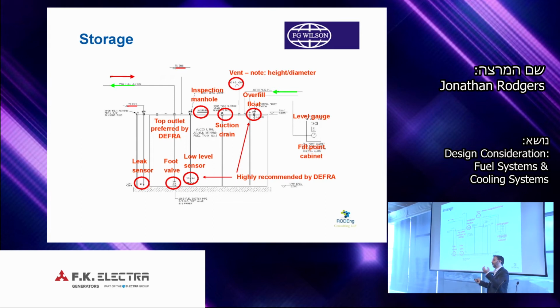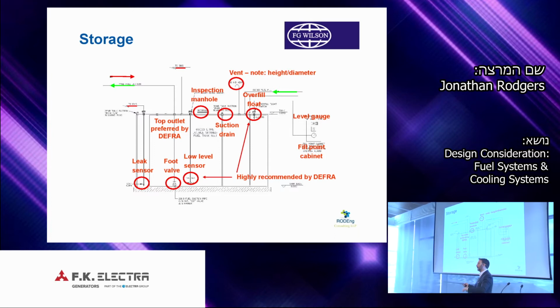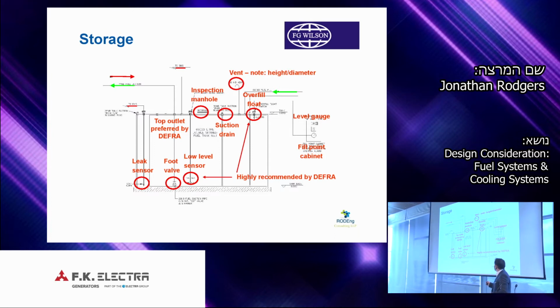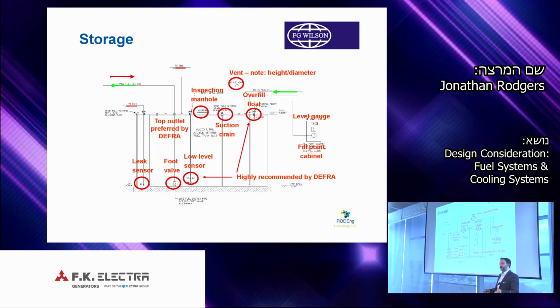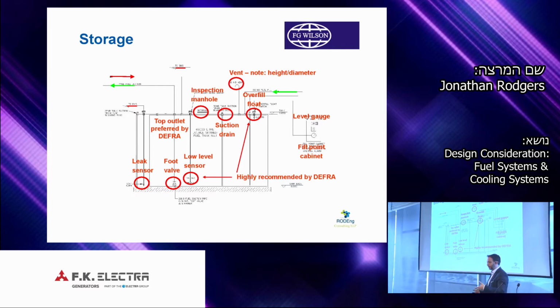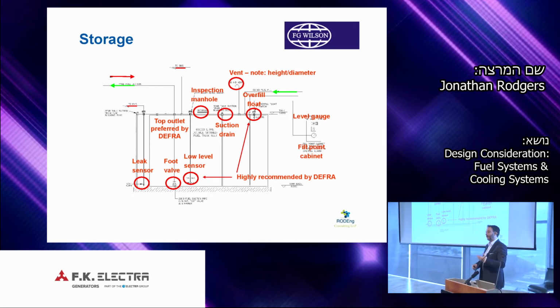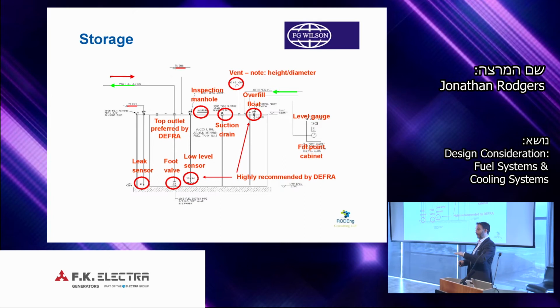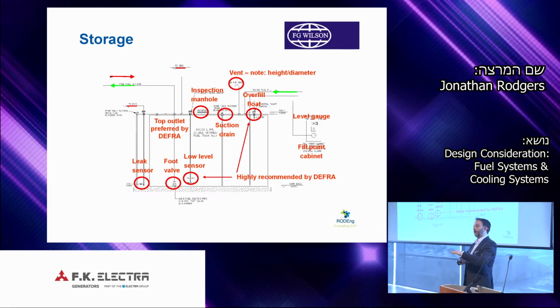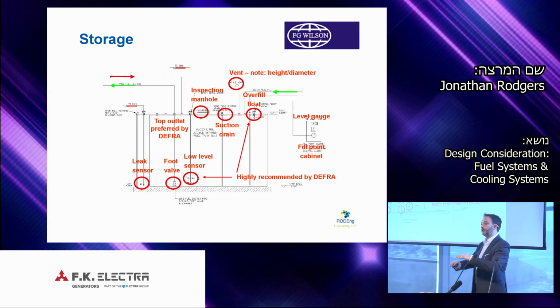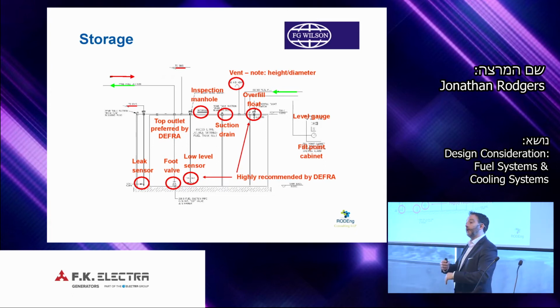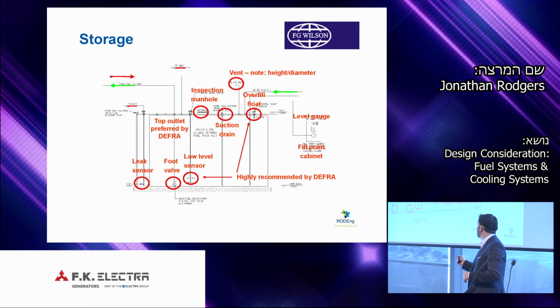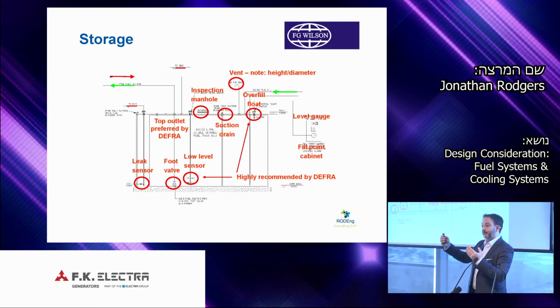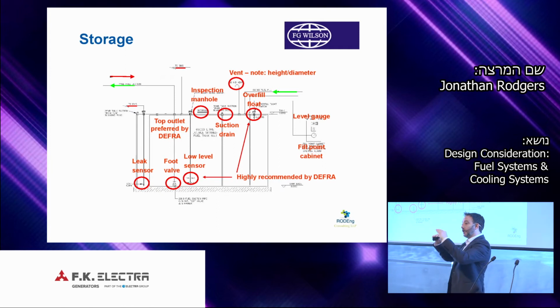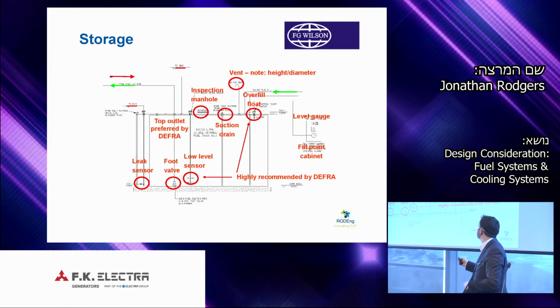Normally, when we're taking fuel from a tank, the preference is to come out the top so you can control it if there is a leak. We do multiple sensors in tanks. More commonly, we will have 4 levels. So we'll have a low level when the tank is becoming low. We'll have a low level that will then stop the generator, inhibit the generators, so you don't pull air into the engine and lock the engine. We'll have a high level to say that the tank is full, and a high level is an alarm and shutdown to stop overfill prevention.